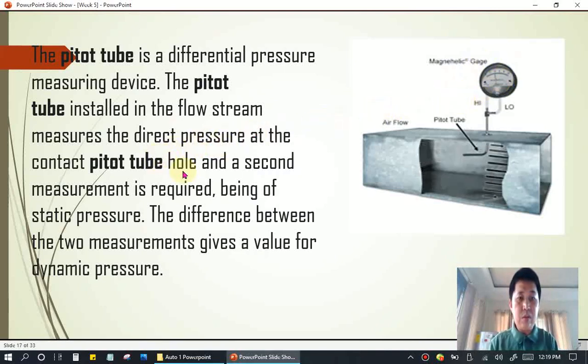It is the direct pressure at the contact that is measured, and the difference between the direct pressure and the static pressure is measured. Here is the direct pressure and you have the static pressure here, the low pressure. The direct pressure minus the static pressure gives you the value for the dynamic pressure. So dynamic pressure is the movement of the fluid or liquid being measured.